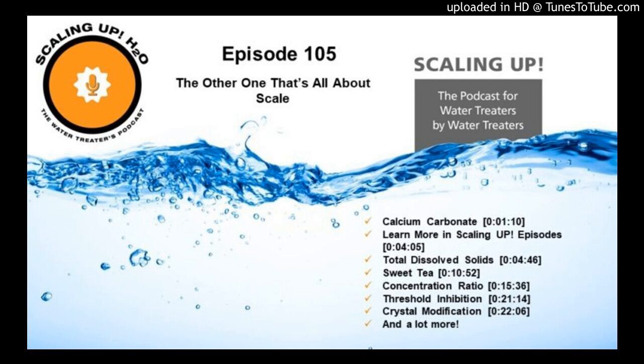So threshold inhibition: if I can keep X amount of a certain product, let's say calcium. So how much calcium do I have in the system? I then test that, and then I'm going to look at my technical data sheet to see how much the water that I'm using with this product can hold in solution.